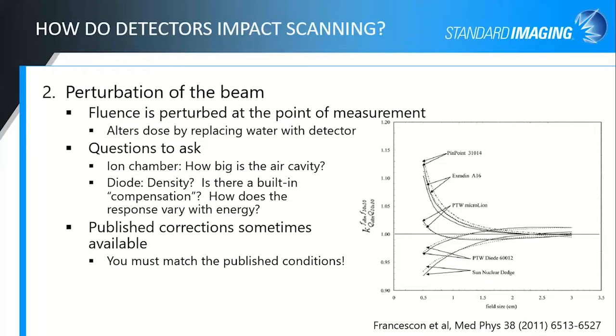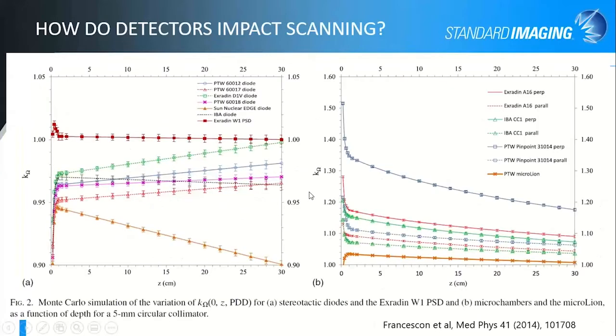There are published corrections. Usually these are related more to the output of your beam than necessarily scanning corrections. But it is important to keep in mind because some of these published corrections can help you understand the behavior of your detector as you move to scanning these small fields, if it's going to under-respond like an ionization chamber or over-respond more like a diode, how to expect that behavior to change. And it does actually affect the tails of the field as well, which I think I have a note on here later on. These are a couple of published corrections on some various detectors with depth for scanning fields, just as a reference from Paolo Francescon.